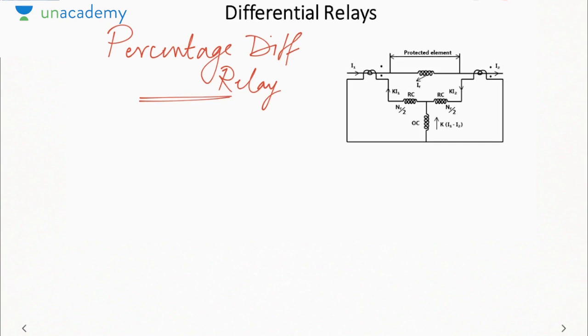In the percentage differential relay, what we do is we have two additional coils called restraining coils. So basically we are increasing the restraining term. Why are we doing this? If you increase the restraining term, you are basically increasing the pickup value. If you are increasing the pickup value, essentially what you are saying is the difference between the two currents must be high in order for the relay to operate. And the difference can only be high in the event of a fault. For minor saturation and other problems, there will be a difference between the two currents, but it won't be high. So the relay will only operate if the difference is high. That can only occur when there is a fault.